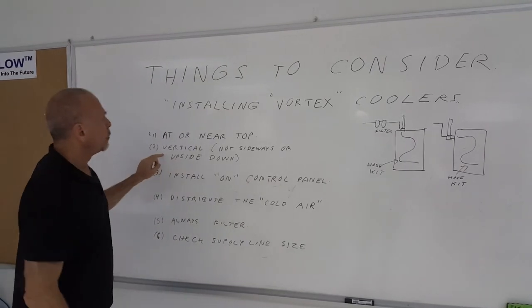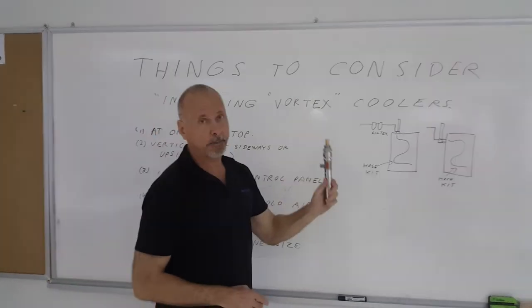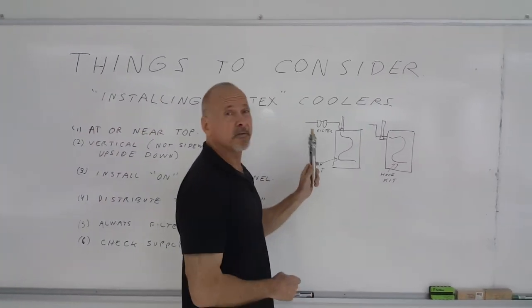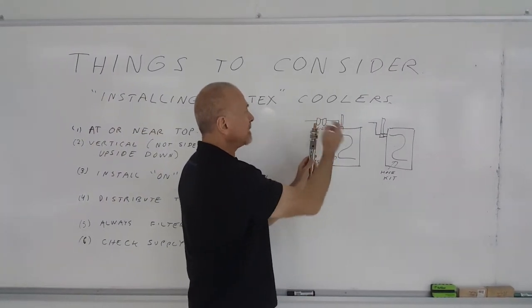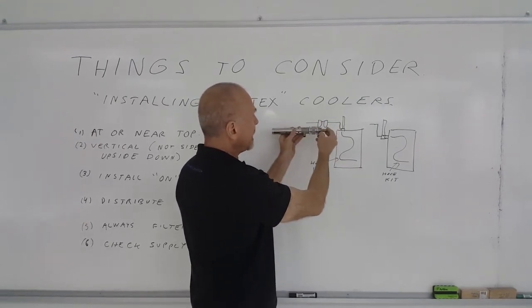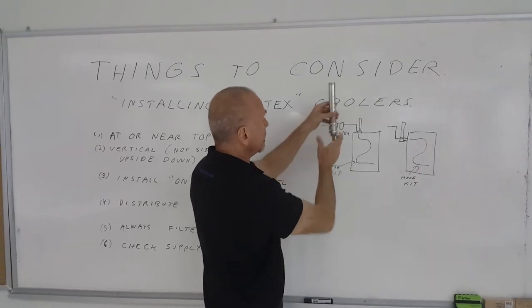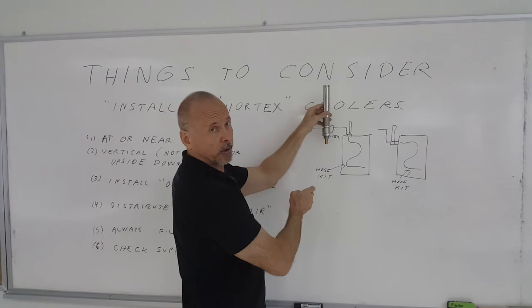Secondly, you want it mounted vertical. You do not want to mount it sideways. You don't want to mount it upside down. Again, for the very reason you want to have that vent to be able to push that hot air out. Mounting it sideways, it's not going to work as well, certainly not very well upside down. So you want it mounted vertical, or at least near vertical.